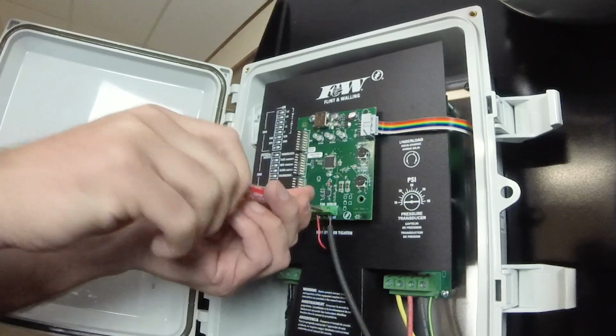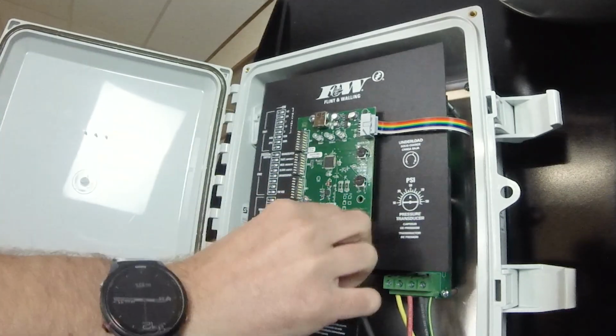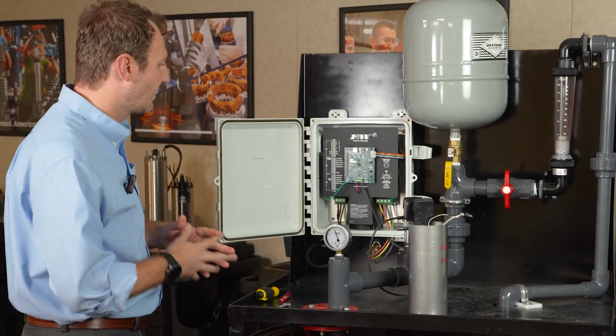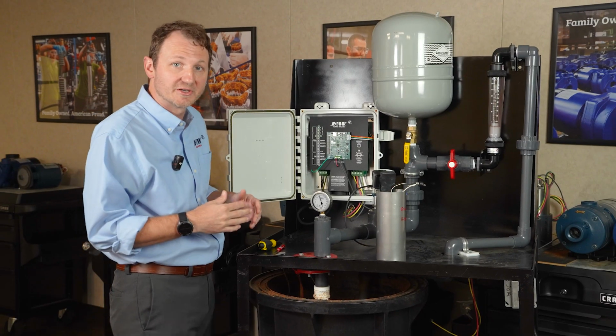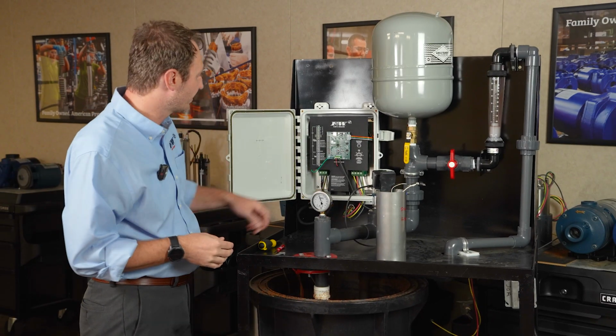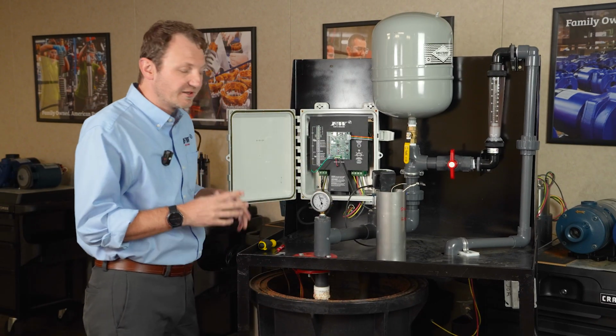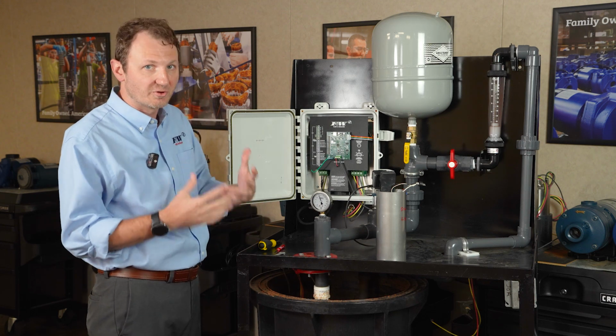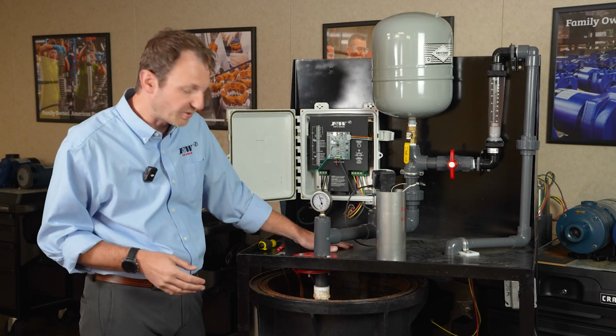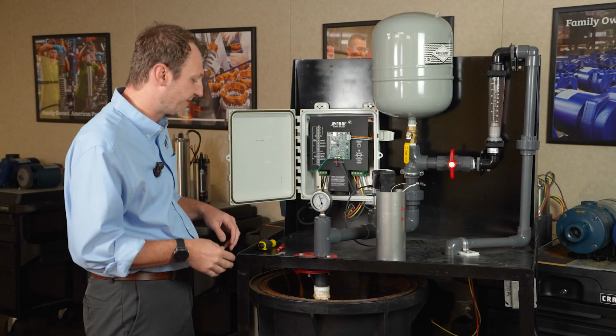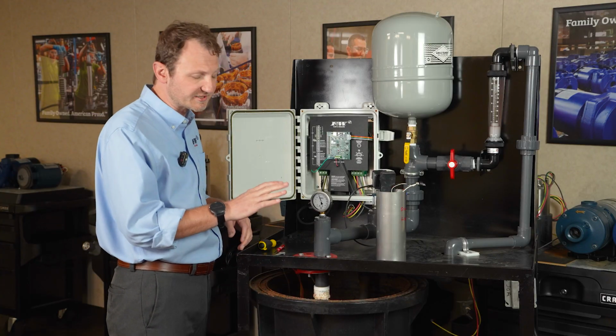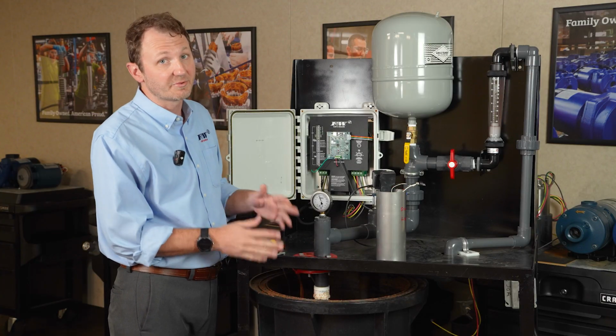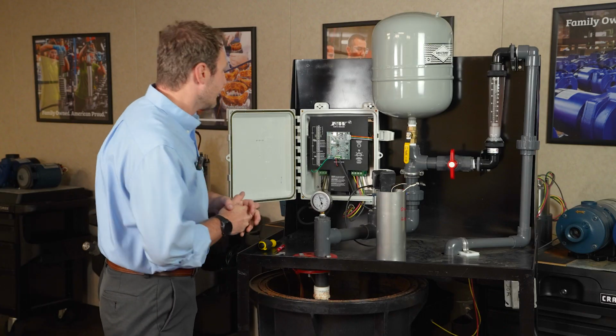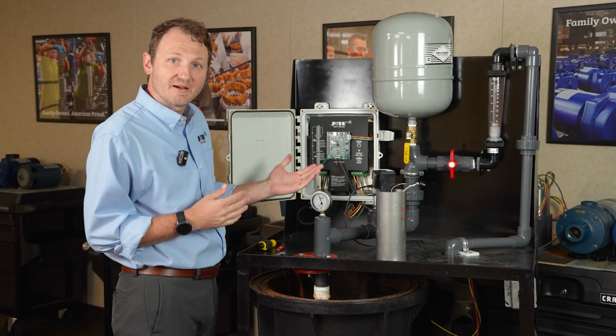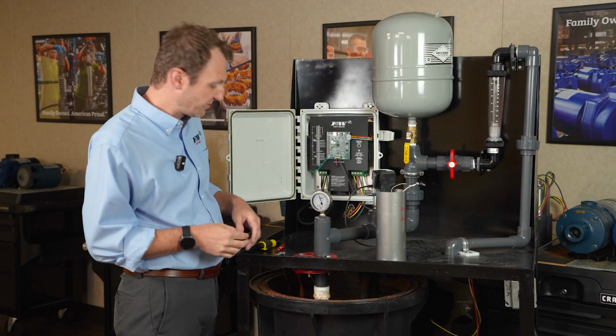All right, so we've got our incoming power hooked up, output to our motor hooked up, we've got our transducer hooked up. The only thing we've got left to do is program this thing to run the pump that we've got down here in this pit. So what we're running down here is a 3-wire, 3-phase, 1.5 horse motor. So what I'm going to do is just set this up to run that motor.